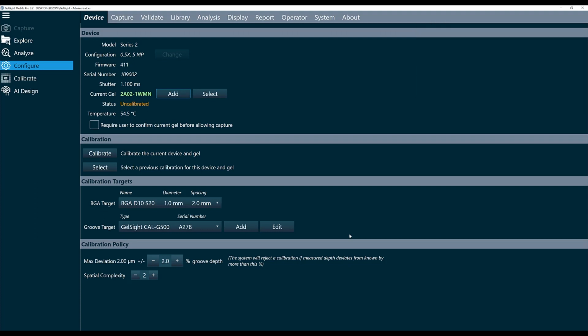My groove target has a serial number of 278, and I can confirm that my target in front of me also says 278. This groove target is NIST traceable and comes with a certificate of calibration. Your kit will include an envelope with a copy of that certificate. We want to make sure that the depth specified on your certificate matches the depth of the target that's in the software.